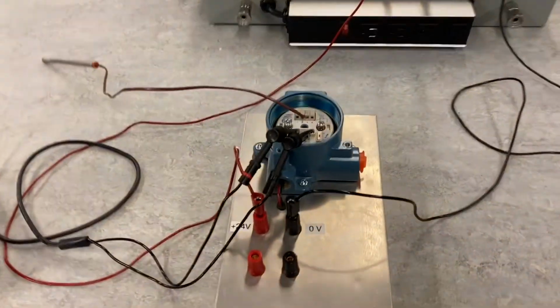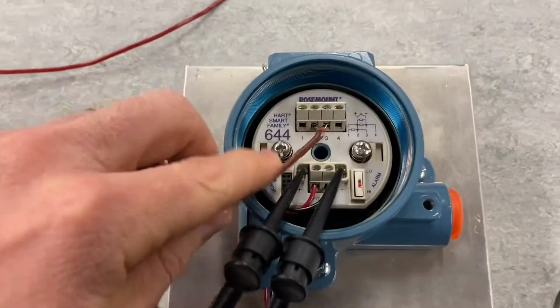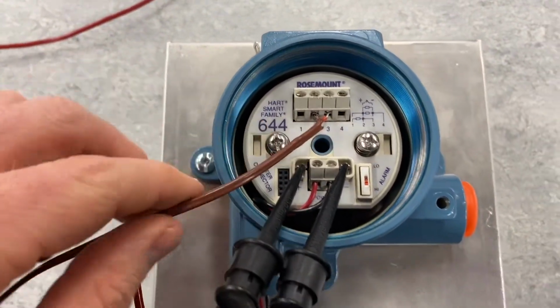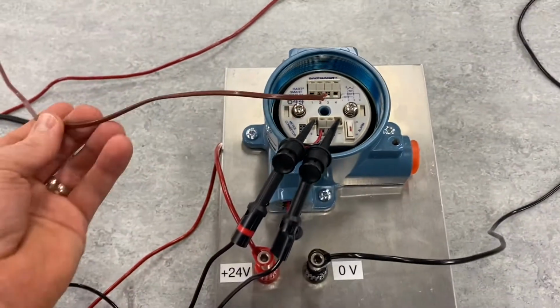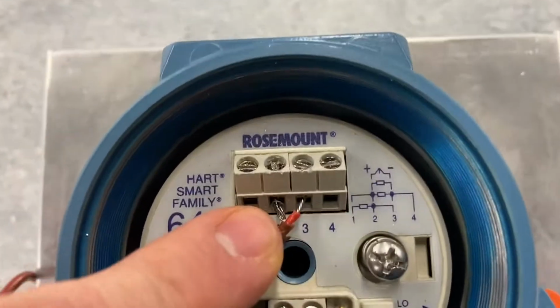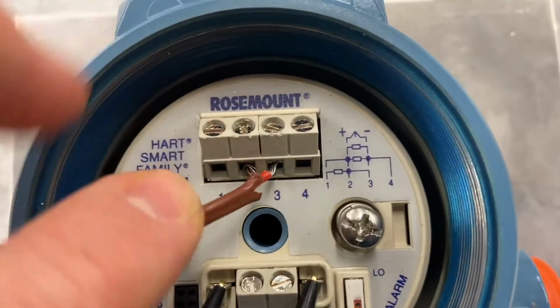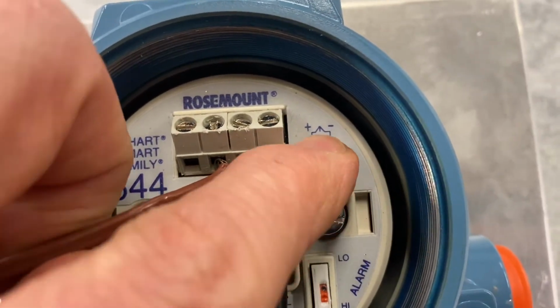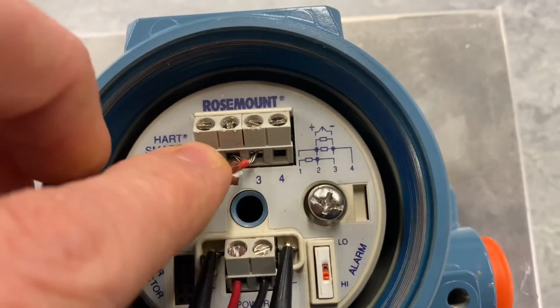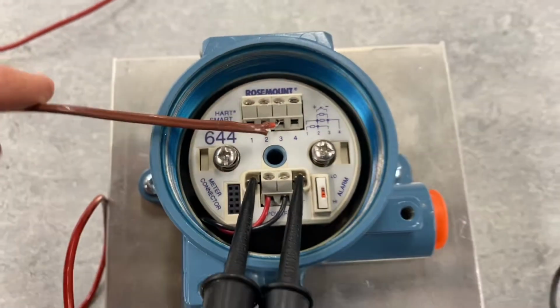All right, so in the last part of this lab, we're switching over to the Rosemount 644. This is a smart transmitter. It has the thermocouple tables and everything stored in it. So we've wired in a type J thermocouple here. You can see across terminals 2 and 3 right here. It shows over here in the diagram for a thermocouple plus minus, red being the minus again, or the negative lead.